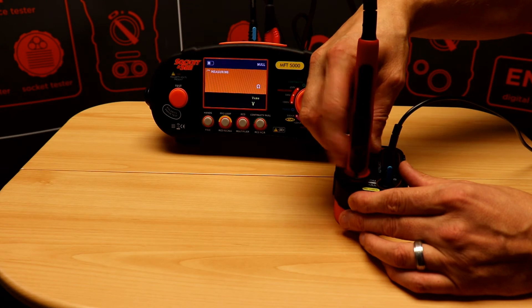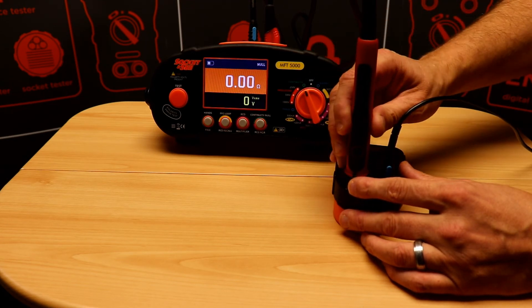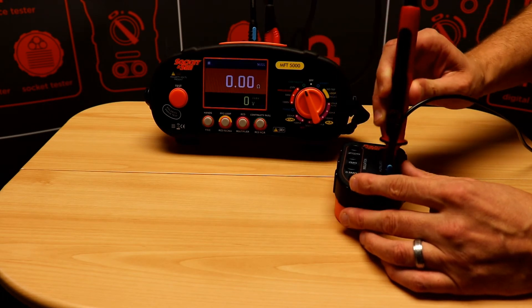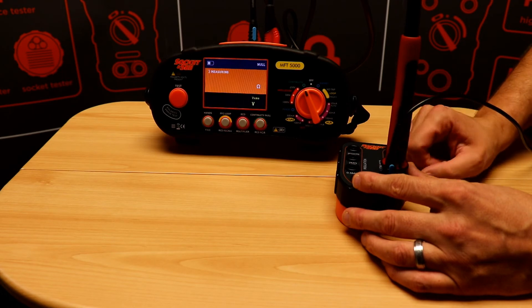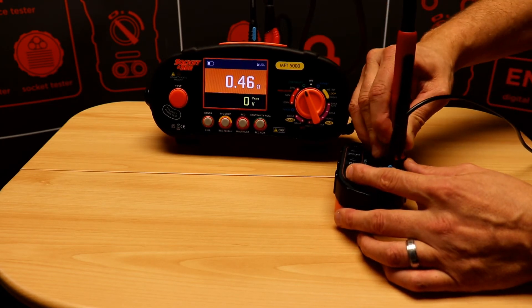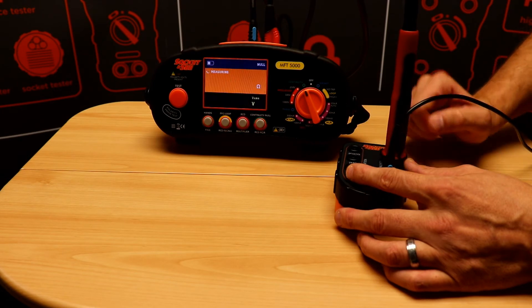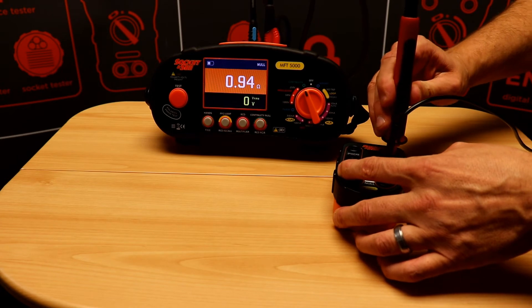If we perform another test we should be getting a zero reading, and then when checking for continuity I'll move up the resistive scale. This should be approximately 0.5 ohms. The next one should be approximately 1 ohm, and finally approximately 2 ohms.